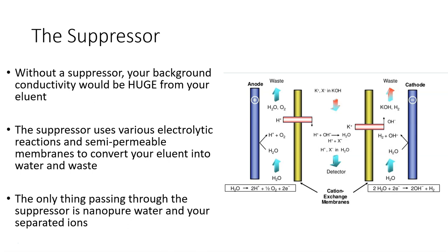The example on the right here shows a sample leaving an anion exchange analytical column in a potassium hydroxide eluent. The electrolytic reactions taking place on the sides here convert your base into water and your cations into waste. It's not super important to understand all of these reactions, but it's important to understand that the suppressor is essential to getting good conductivity measurements.